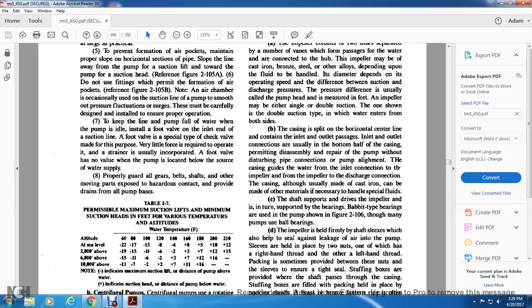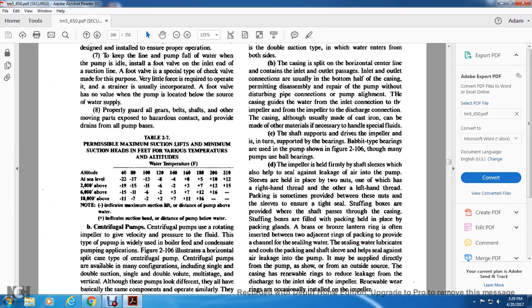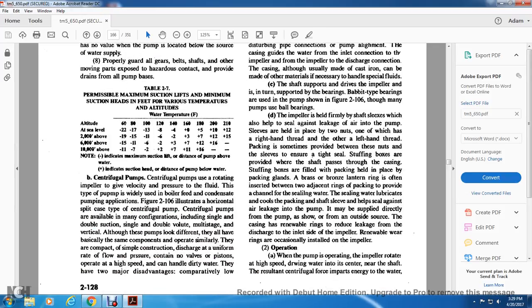The casing, although usually made of cast iron, can be made of other materials necessary to handle special fluids. The shaft supports and drives the impeller and is held by the bearings. Babbitt type bearings are used on the pump as shown in Figure 2.106, though many pumps also use ball bearings. The impeller is held firmly on the shaft, and sleeves help seal against leakage into the pump. The sleeves are held in place by two nuts, one with a right hand thread and the other with a left hand thread. Packing is sometimes provided between the nuts and the sleeve to ensure a tight seal at the stuffing box where the shaft passes through the casing.